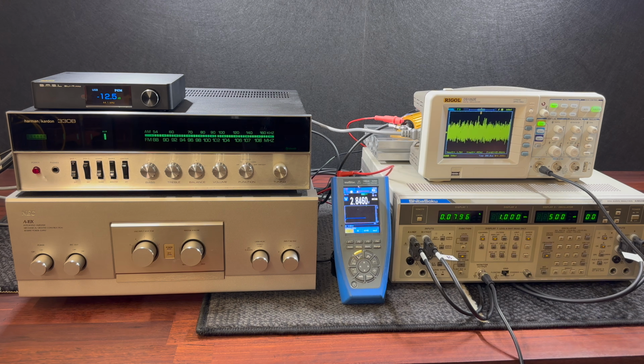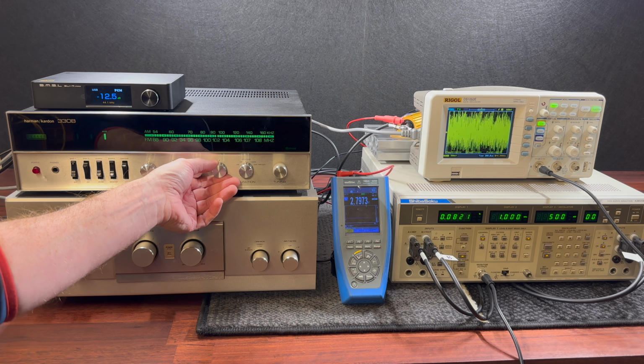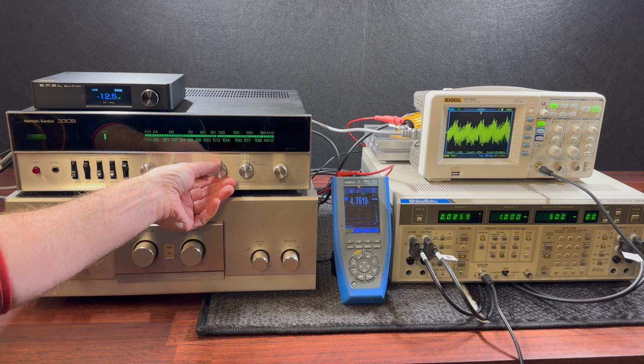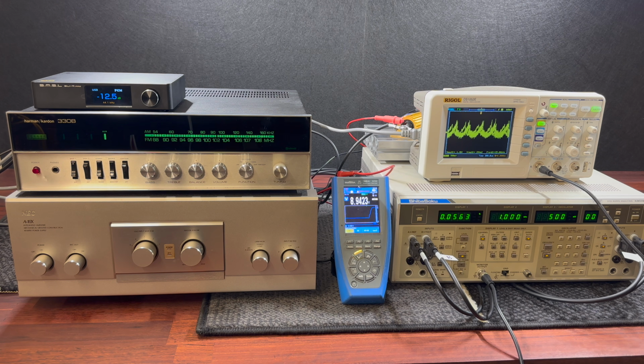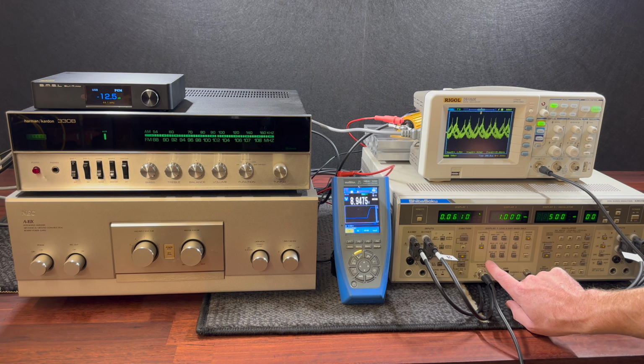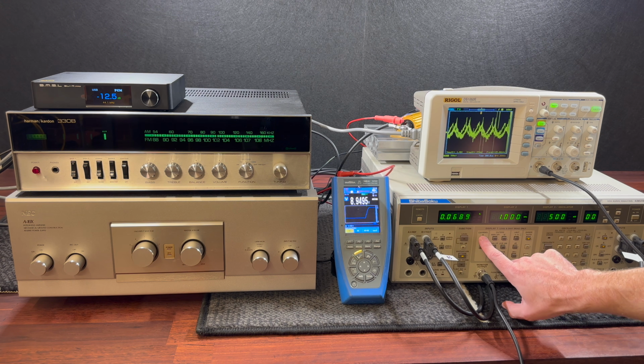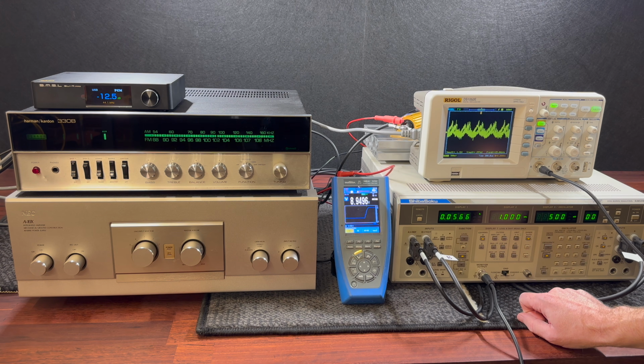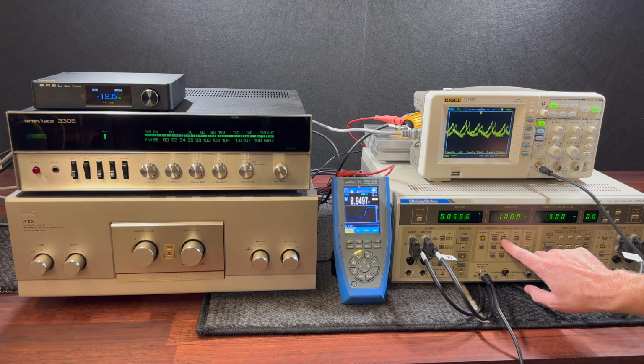We could try a 400 Hertz high pass filter if we want to see if there's any power supply noise. And yeah, so that's 1 watt per channel. So let's take it up to 10 watts, which is 8.9 volts and 0.05%. And between the channels, 0.06. So it's a little off between the channels, not too bad.